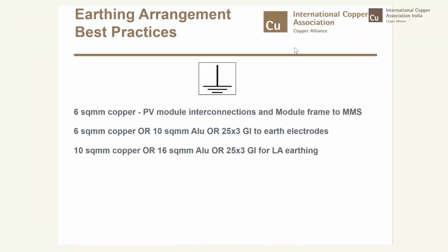We'll move on to the best practices on the earthing arrangement. Here we see we have to have 3 types of earthing in a rooftop system. The first is all the DC earthing. All the DC side has to be earthed. That is the DC module and the array structure, and maybe junction boxes or the DC distribution box. All this forms the DC subsystem. So the DC subsystem components have to be earthed using not less than 6 square mm copper conductor, and they also need to be interconnected to create equipotential bonding.